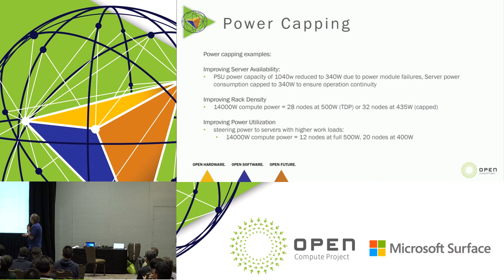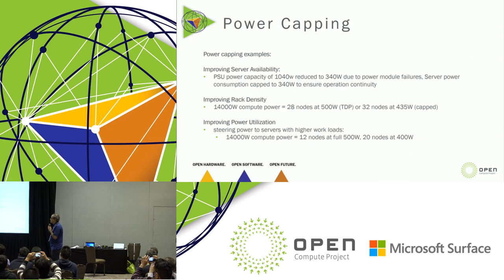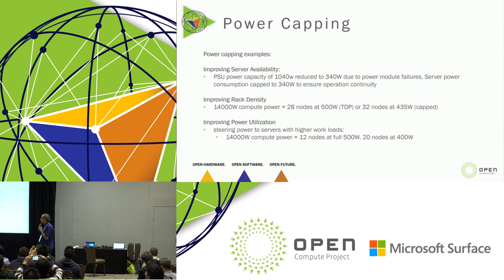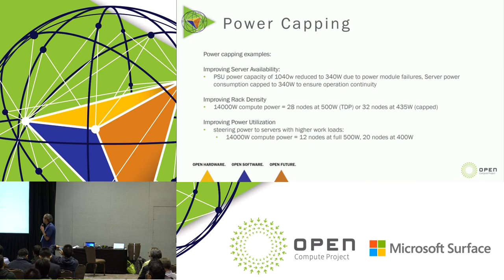Here are a couple of examples showing how we can leverage power capping to improve server availability. We discussed the Project Olympus power supply providing a total power of 1,040 watts. But if there is any hardware failure or AC loss causing capacity to drop down to 340 watts, we can use power capping to cap the server to 340 watts and continue operation.